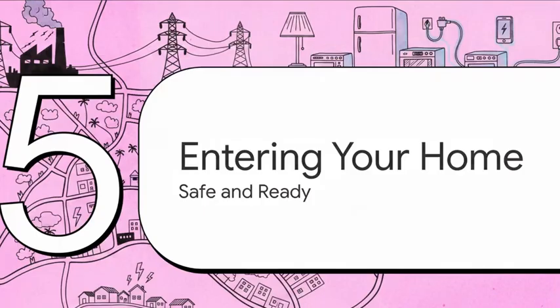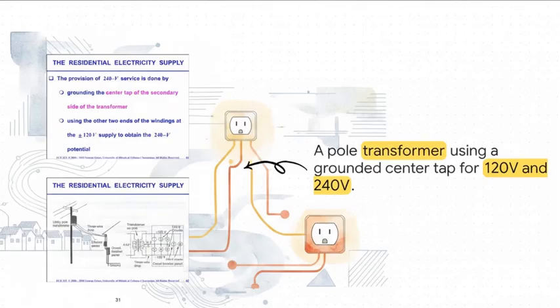And finally, part 5, entering your home, safe and ready to use. This final connection is just such a brilliantly clever piece of engineering. That utility pole transformer uses something called a grounded center tap on its secondary side to literally split the voltage. This design gives us the standard, much safer 120-volt circuits that we use for lights and regular wall outlets. But at the same time, it allows the outer two ends to combine and provide a beefier 240 volts for heavy-duty appliances, like your oven or your clothes dryer.